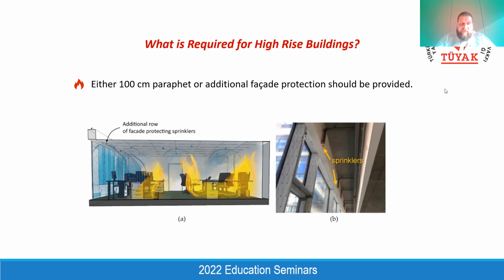That's why if you are not providing 100 centimeters of parapet between each floor, you need to inform the mechanical designer to process their design to have closely located facade protection sprinklers. Otherwise, when you finalize the project and when you are trying to hand over to the owner during the, I don't know the exact name, ruhsat phase, when you are trying to get the permit for your building, when the local fire brigade comes and if they see that there is no parapet, they directly require the closely located facade protection sprinklers. It may postpone the opening of your building. They are really strict on this issue. That's why it is also your responsibility as an architect to decide whether you will have a parapet, or you need to inform the mechanical designer accordingly.